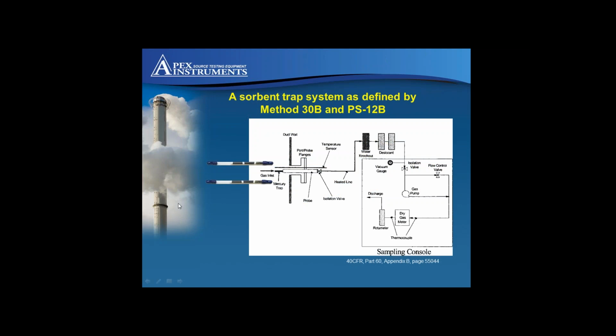The image on the screen is taken directly from Method 30B, showing a Sorbent trap monitoring system. We've added a picture of the Sorbent traps here for a point of reference on the system. To give everybody the basic understanding, sample gas is pulled through the set of traps at the end of the probe, which is inserted into the stack gas stream. The mercury is collected on the carbon media within the traps. The sample gas then flows through the probe, down the heated line, to a moisture knockout system, creating a dry sample. The sample is then sent to the dry gas meter, which records the sample volume so it can be compared to the volume of mercury collected to produce a time-weighted average value of the mercury in the source.